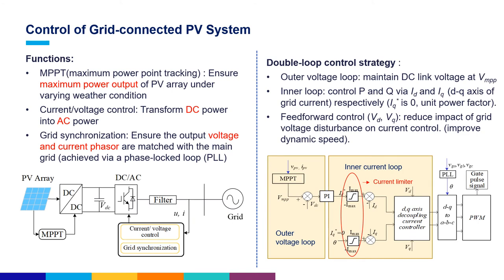The protection issue caused by PV generation mostly relies on its control system. As can be seen from the diagram, the PV system is mainly composed of a PV array, a DC-DC boost converter, a large DC link, an AC inverter, and a filter. The control system has three main functions: first, the MPPT, realized by the maximum power point tracking algorithm, which ensures maximum power output under varying weather conditions; second, the current/voltage control, which controls the inverter to transform DC into AC power; and third, grid synchronization, which ensures the output voltage and current phasors are matched with the main grid using a phase-locked loop control.